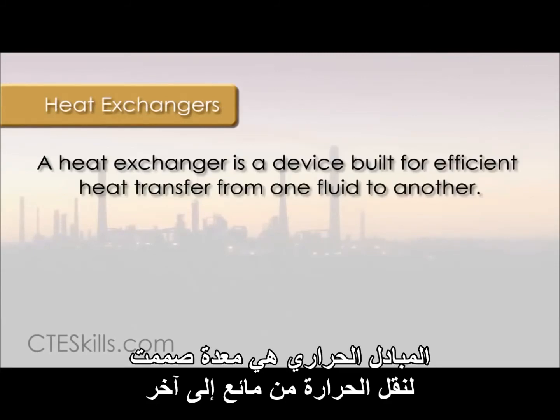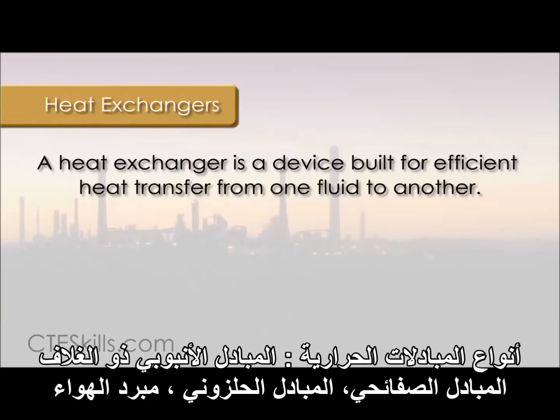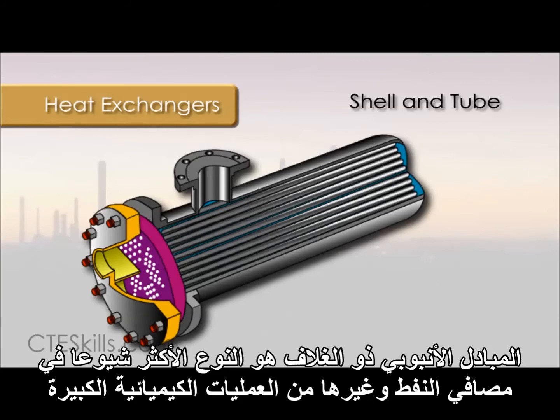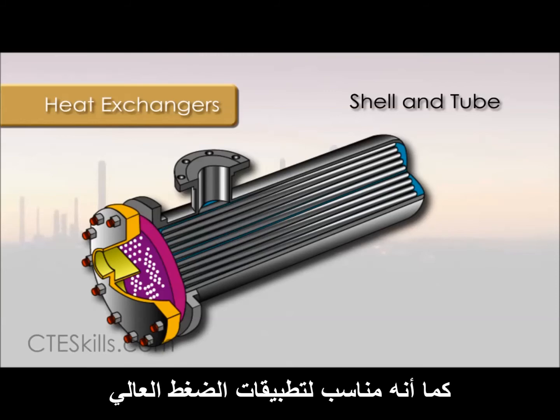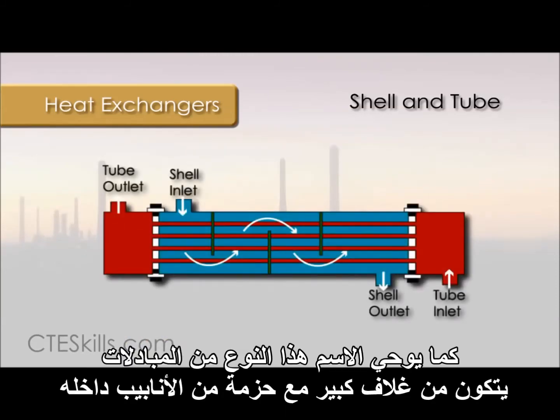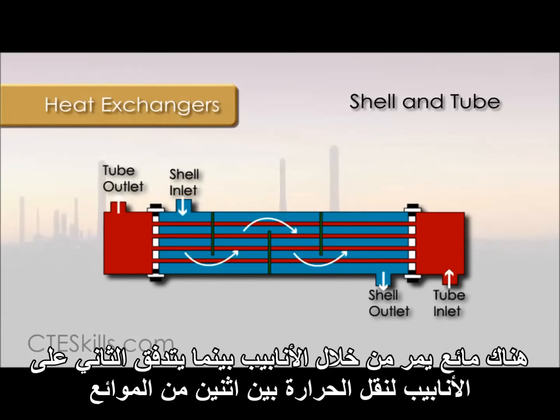A heat exchanger is a device built for efficient heat transfer from one fluid to another. Heat exchangers are generally classified as shell and tube, plate, spiral, or air-cooled. A shell and tube heat exchanger is the most common type of heat exchanger in oil refineries and other large chemical processes, and it is suited for higher pressure applications. This type of heat exchanger consists of a large vessel or shell with a bundle of tubes inside it. One fluid runs through the tubes, and the second runs over the tubes to transfer heat between the two fluids.